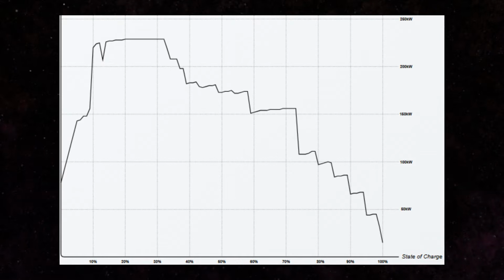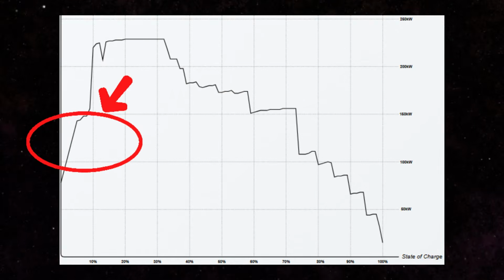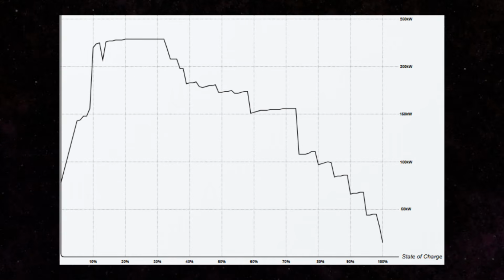The average C rating of 1.67 C aligns with the sustained 150 to 165 kilowatt window you see through most of the mid state of charge range. The detailed state of charge table shows a rapid ramp. Early on, 0 to 9%, speeds are modest, 78 to 156 kilowatts. Then at 10%, the curve jumps to 220 kilowatts and stays near 229 kilowatts across the 20 to 33% band.